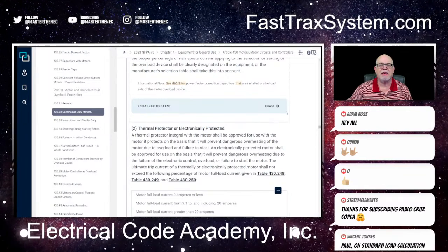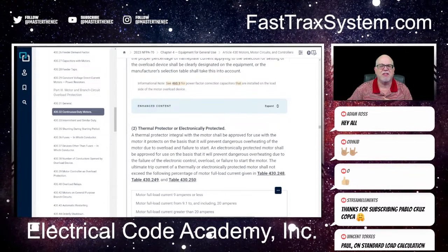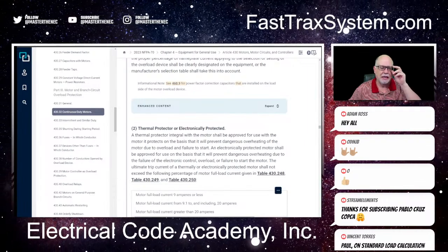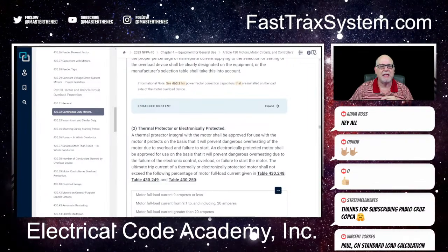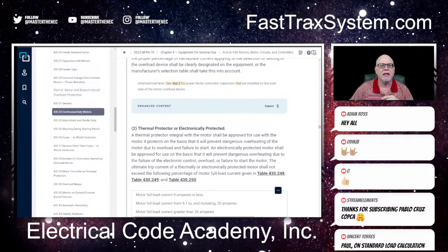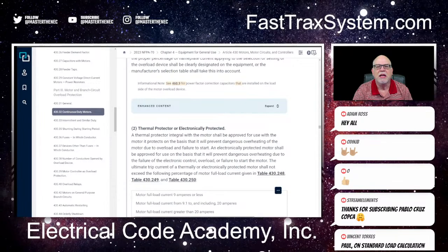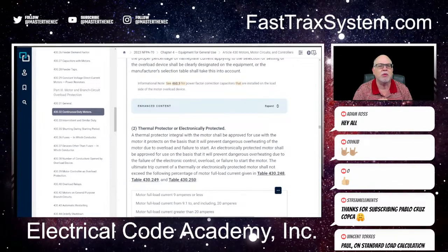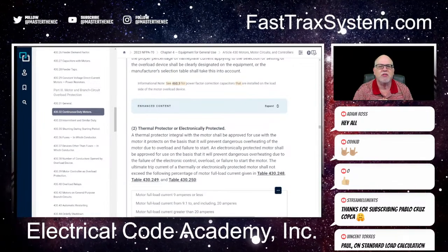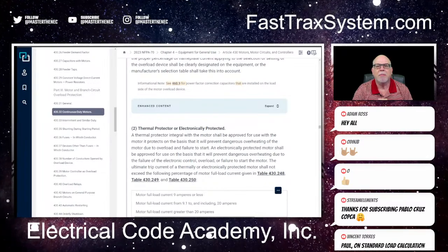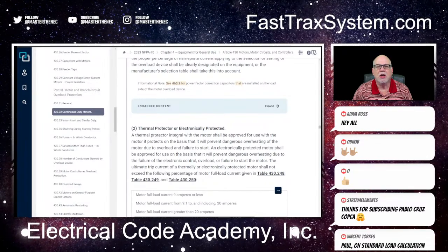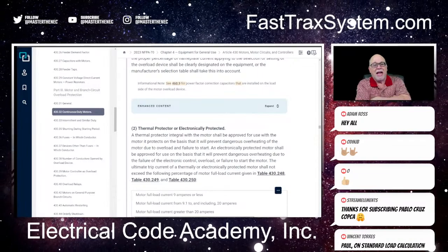All right, let me see if I can get back real quick and get some of the questions that I had. I can't scroll back your screen, but I can scroll back and see what we got. Okay. Vincent says, Paul, on standard load calculations, how do you account for the range receptacle that is installed, but the customer has a gas appliance installed currently? Okay, well, how would I account for that?